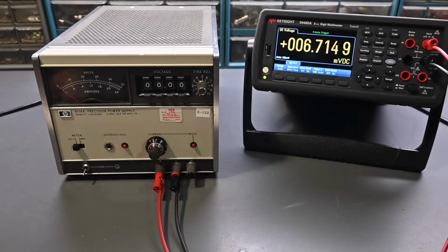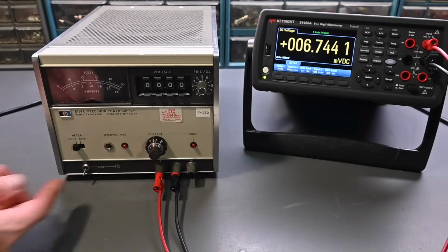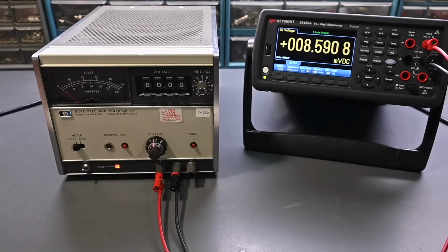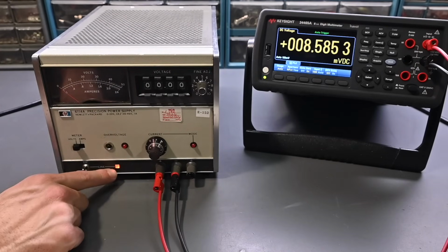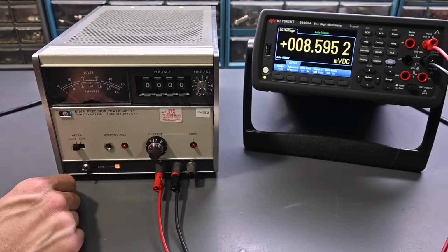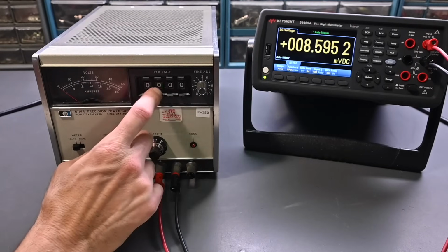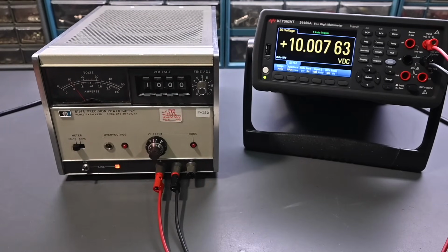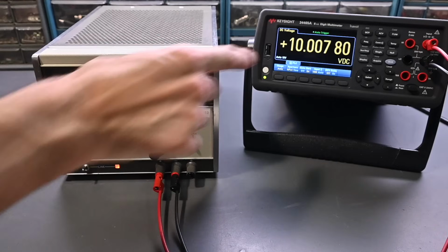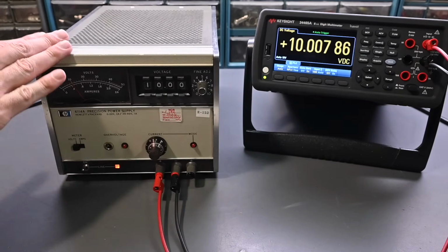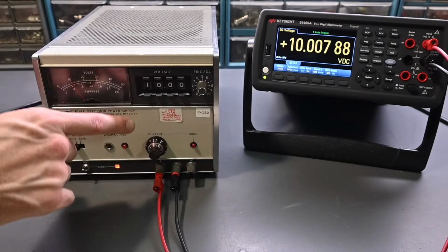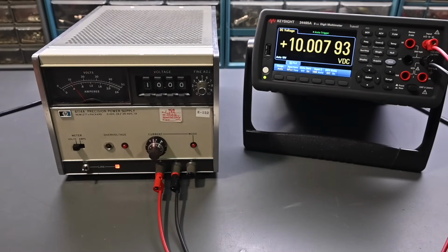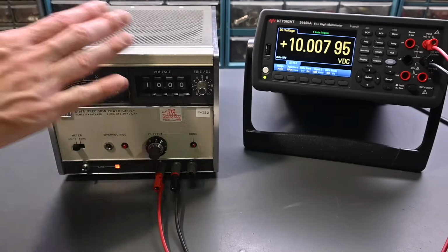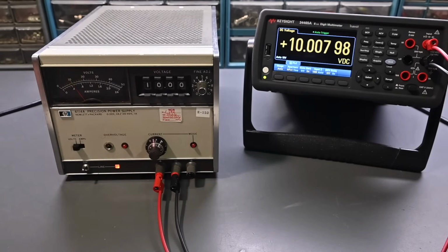All right, so get the AC line switched on there, and here we go. So it turns on, we have power on indication right there. And right here, let's just say we go to 10 volts, and that's normal, so we have 10 volts over there. Now, I'm sure this needs some calibration, maybe to dial things in a little closer. It's sitting at what should be 10 volts, and it's about 7 millivolts high right now. Also, this needs to warm up and stabilize, and of course, I'm just turning it on right now, so it hasn't had a chance to warm up.